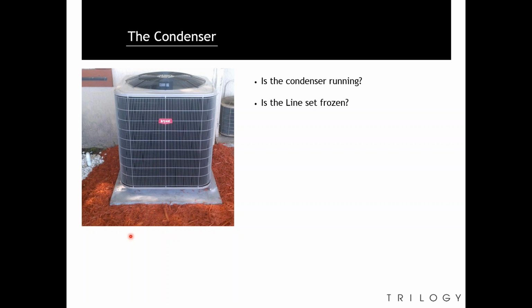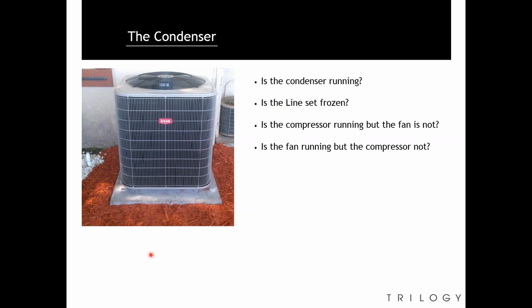Is there line set? Is it frozen? Is there ice on the line set? Is the compressor running but the fan is not? Is the fan running but the compressor is not? You check the line set. The line set, is it cold? Is it sweating? Is the system pulling heat off the top? These are great visuals just walking up to the unit itself to kind of get us started before we head into the inside.